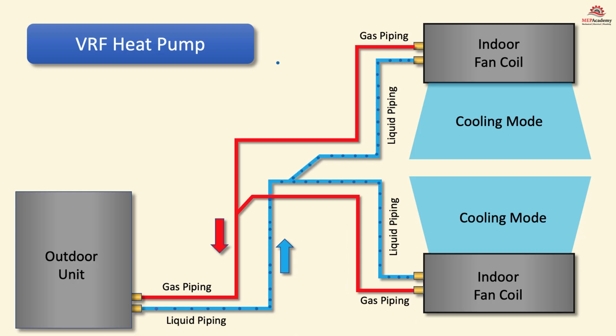All air conditioning systems, including VRF systems, are made to move heat from one location to another depending on the mode of operation. Heat is either brought into the building or rejected out of the building. Using a VRF heat pump in cooling mode, heat is absorbed into the refrigerant from the warm indoor air blowing over the coil. The heat is then circulated by the compressor to the outdoor unit where the heat is rejected through the outdoor coil into the outdoor air. For a complete understanding of the refrigeration cycle, see our video on Refrigeration Cycle 101.